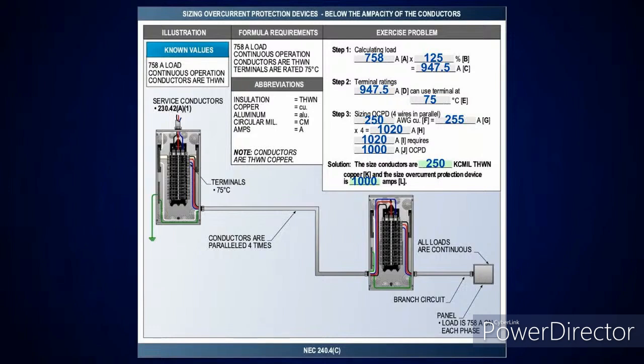So just remember it like this. 240.4B is for overcurrent protection devices that are 800 amps or less. 240.4C is over 800 amps. And the thing you want to remember in 240.4C is that the conductors have to be the same size or exceed the calculated ampacity. So that means you're going to drop down.